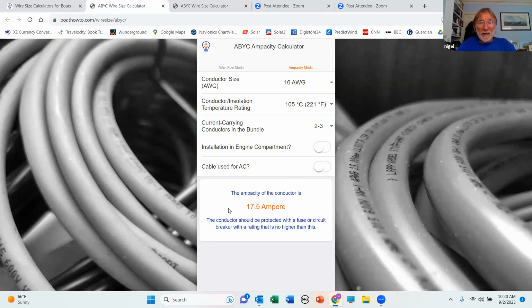That's from a standards perspective, you're allowed to go to the 17.5 amps. From a practical point of view in your boats, you should never push the limits of these systems and go to the maximum you're allowed. And I would recommend when you're sizing conductors in your boat that, even if you're using 105-degree insulation, you use the 90-degree insulation column, because that will give you a bit of wiggle room. And in this case, it still stays at 17.5 amps.